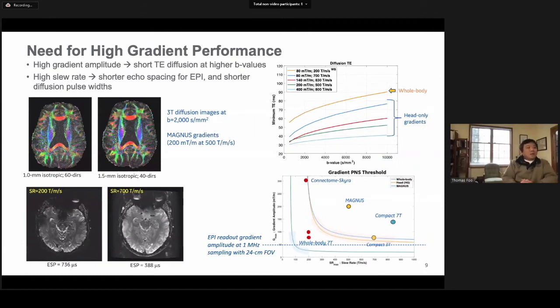The need for high gradient performance is seen in this slide. High gradient amplitude is needed to reduce the TE time for diffusion, especially at high B values. So as you can see here, whole body MRI systems have about an 80 millitesla to 100 millitesla maximum gradient amplitude. So for a specific protocol, in this case the Human Connectome protocol, you can see the TE times range anywhere from about 60 milliseconds all the way up to 90 milliseconds at B10,000.